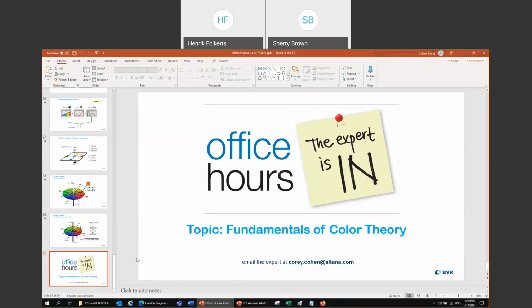I'd say yes, for one, that's always preferred. First of all, I want to make sure you're not confusing the terms illuminant with light source, because those are different terms. The light source that an instrument uses doesn't really matter as far as the color calculation. The light source isn't actually going to use D65 or A or whatever illuminant is being selected.